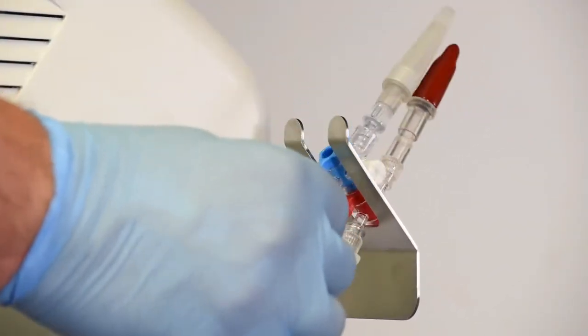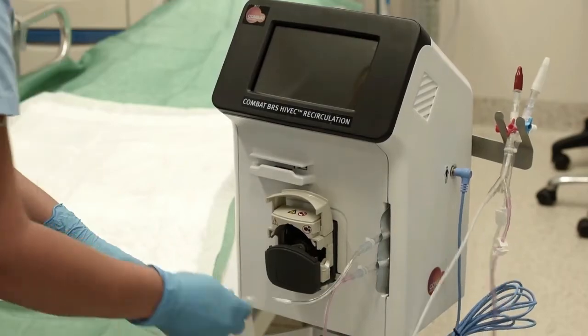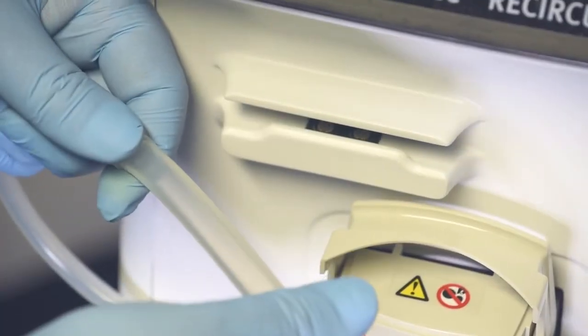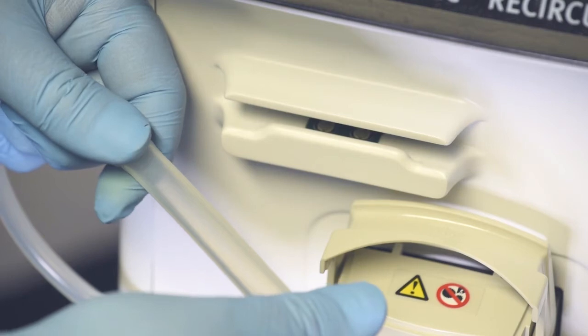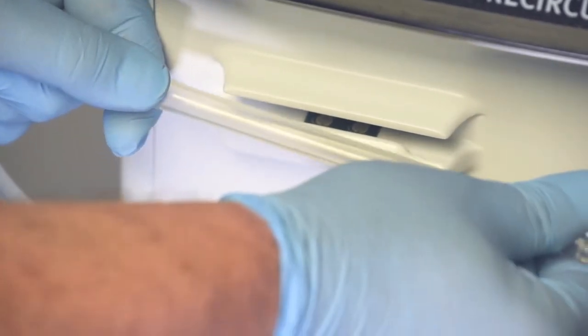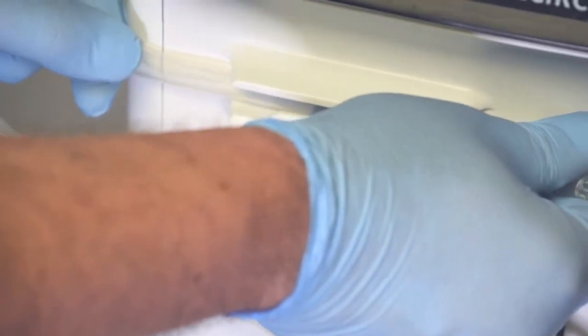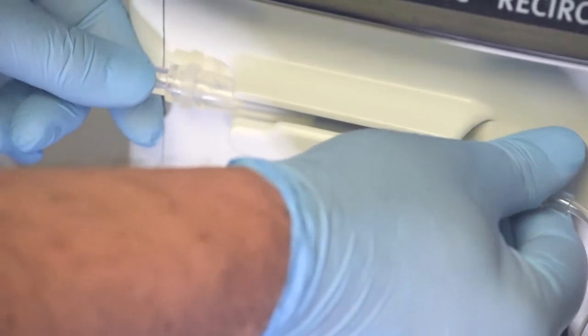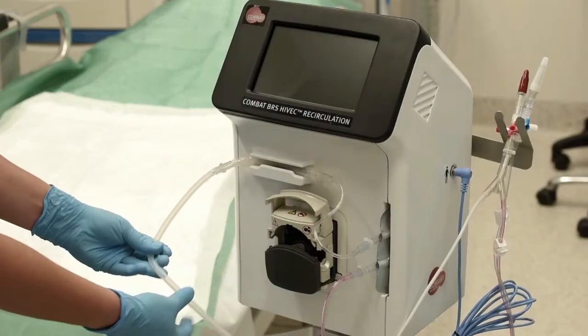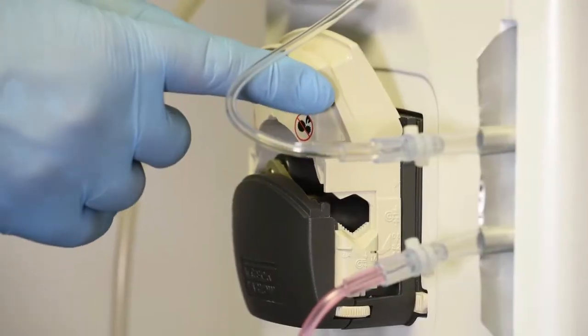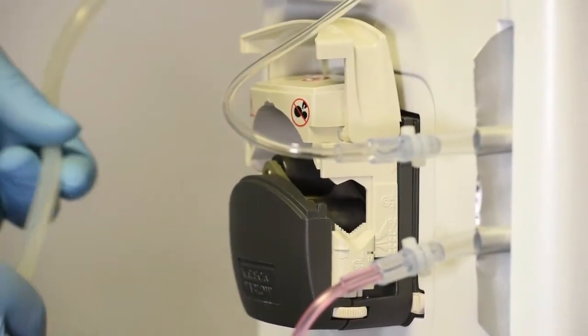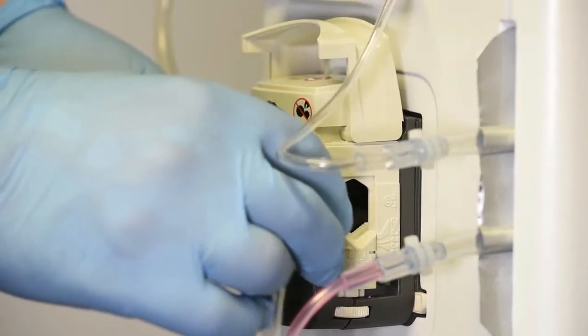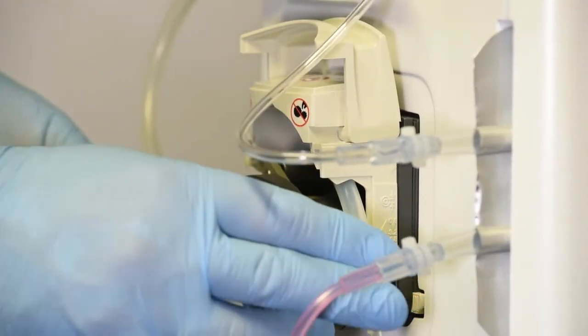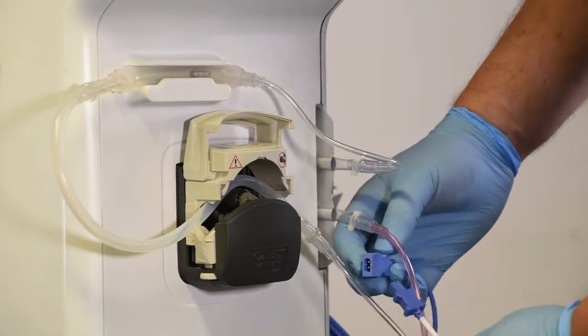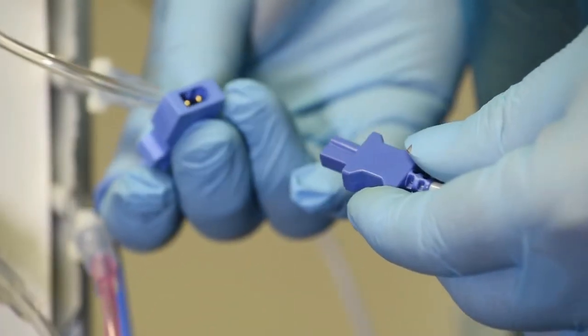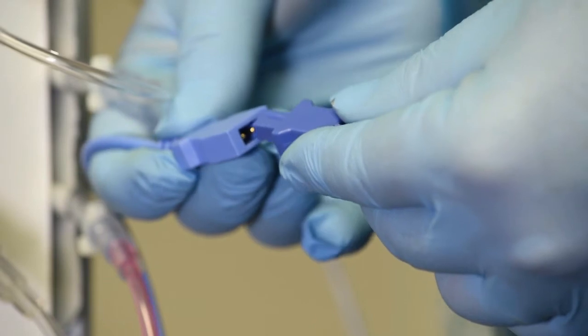Place the short, stout pressure-sensing silicone tube into the pressure sensor housing. To achieve this, hold the pressure sensor tubing at the rings at both ends, stretch the tubing sufficiently to gently roll and insert the silicone tubing into the slots of the pressure sensor housing. Then, place the long, thin silicone tubing into the peristaltic pump. Insert carefully to ensure that the tubing is away from the teeth of the pump cover. Finally, connect the inline temperature sensor of the disposable set to the equipment using the blue temperature cable as demonstrated.